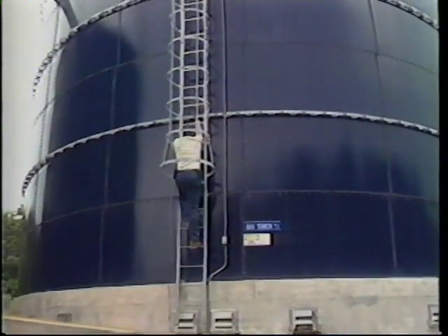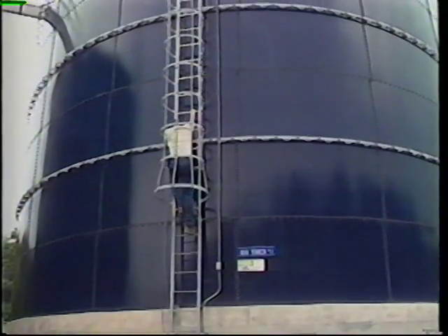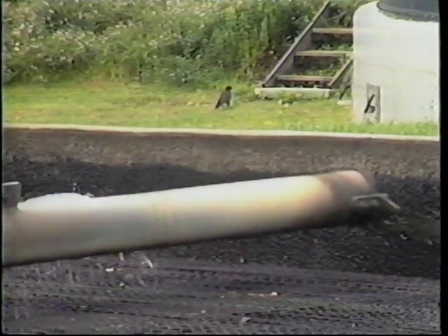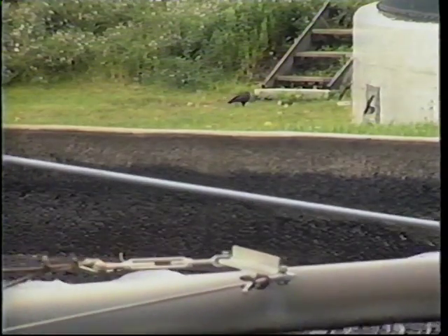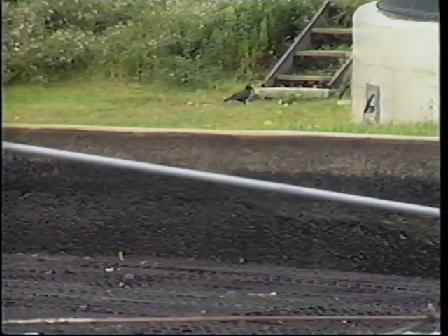The taller filters usually have ladders for easy access. The structure should be inspected regularly and repaired if necessary. Care should be taken to prevent excessive weed growth around the trickling filter structure, as this provides an excellent place for filter flies to congregate.